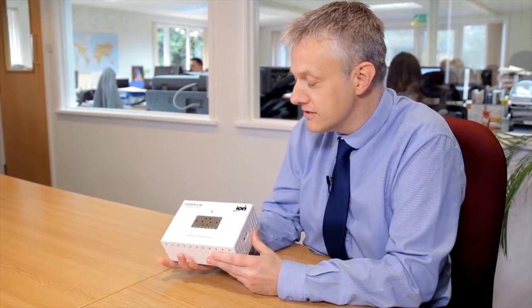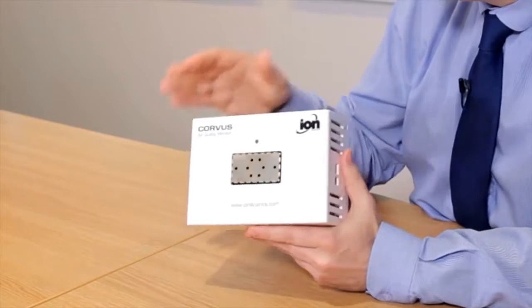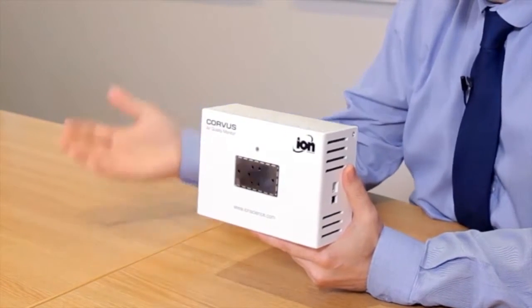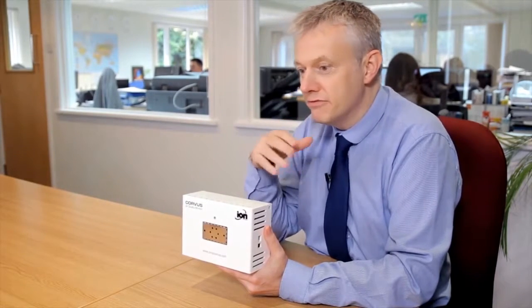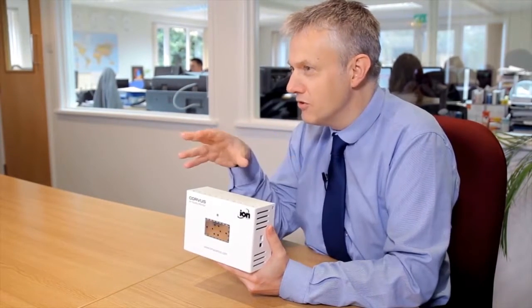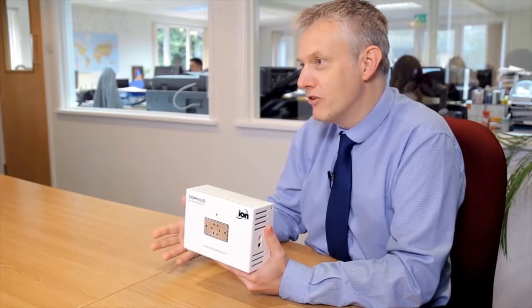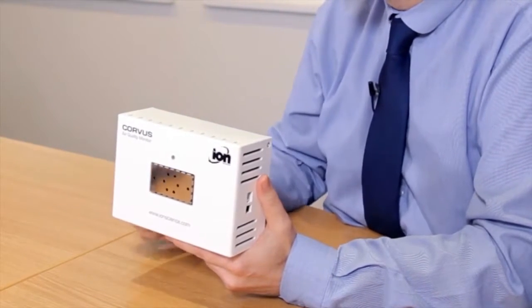One very nice feature is that this is a mesh network instrument. So if for some reason one of the instruments gets isolated and the signal is broken, there's substantial onboard memory. The instrument will take all of the readings, store them on board, and then when the wireless is regained, transmit and pass them on again. If the trial is quite long term, you can deploy an entire group, return periodically, plug in a USB, and capture the entire data set all from one instrument — so it's really quite quick.